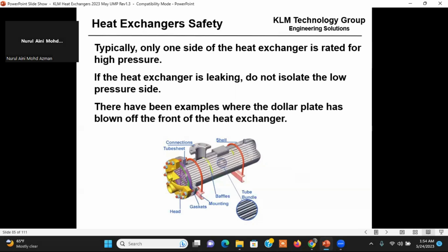Heat exchanger safety. Typically, only one side of the heat exchanger is rated for high pressure. If the heat exchanger is leaking, do not isolate the low pressure side. There have been examples where this dollar plate has blown off the front of the heat exchanger. All right, so be careful. A lot of times in HAZOPs now we'll put a relief valve on this low pressure side. Okay, all right.